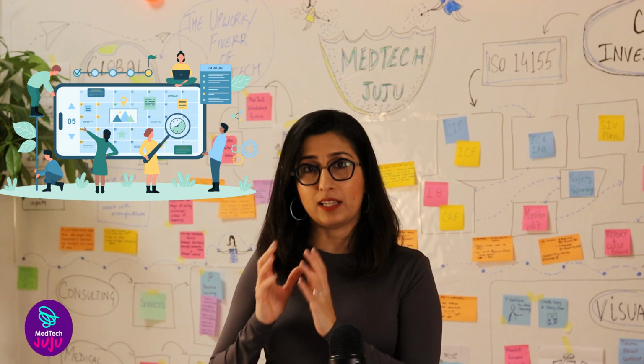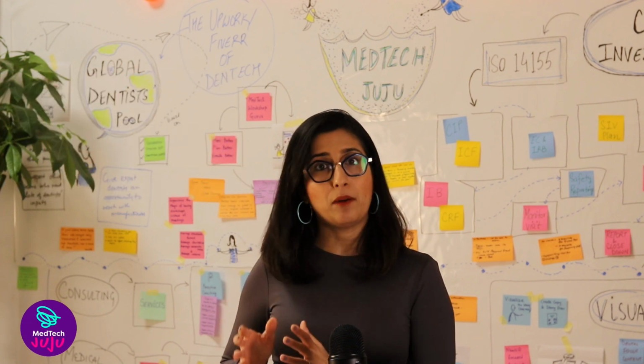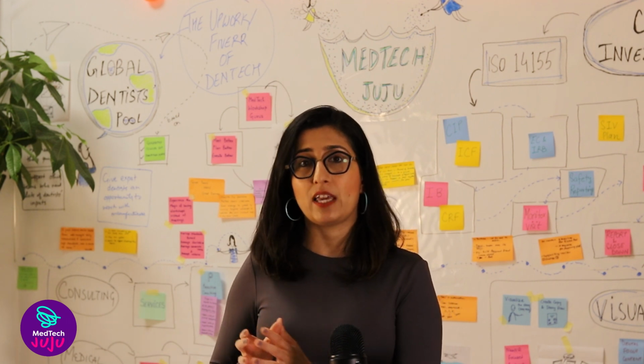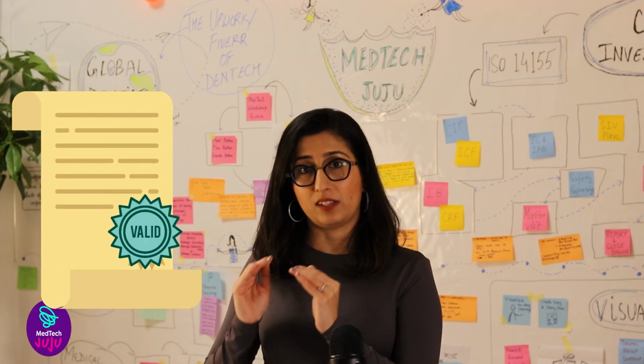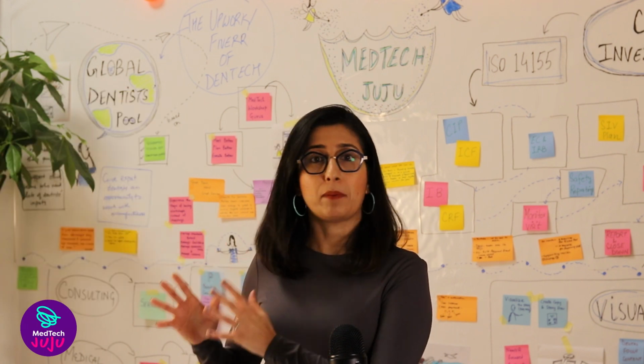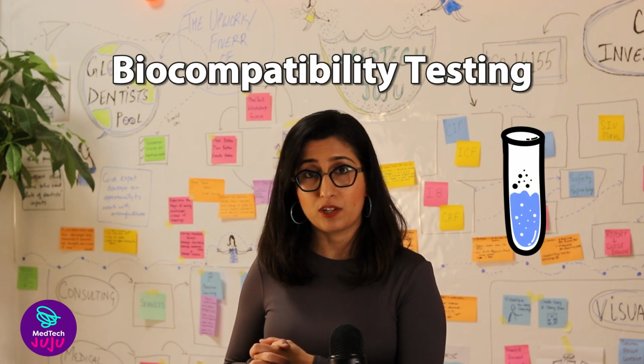And they're running lab tests which have to be done. There's no way around it. It is a requirement by the regulations. Every medical device needs to have a verification and validation, which is a series of lab tests that need to be done at certain independent parties. This can also include the biocompatibility testing for your device.